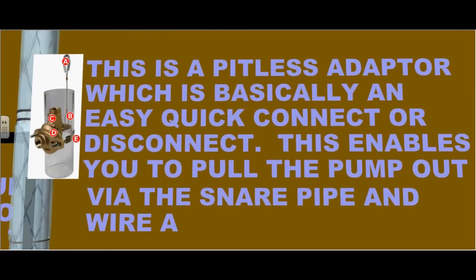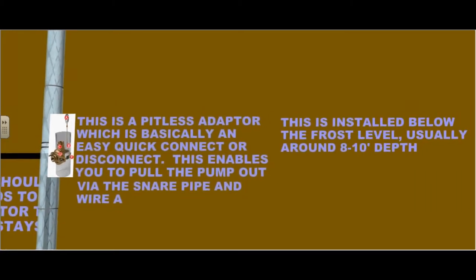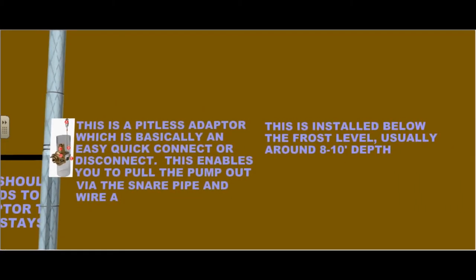This is a pitless adapter, which is basically an easy quick connect or disconnect. This enables you to pull the pump out via the suction pipe and wire assembly. This is installed below the frost level, usually around 8 to 10 feet in depth.